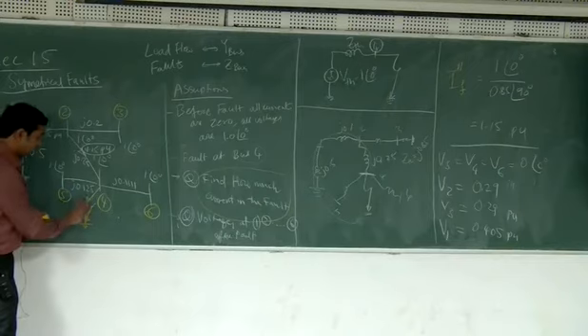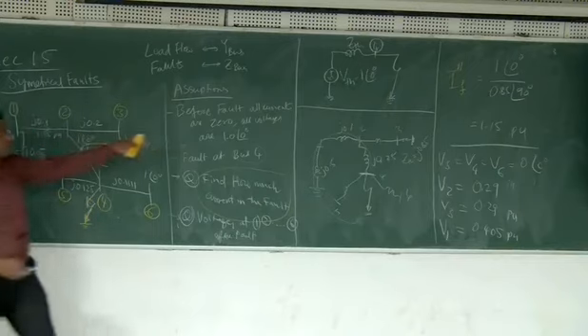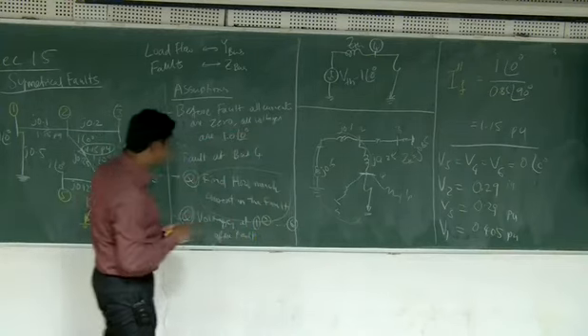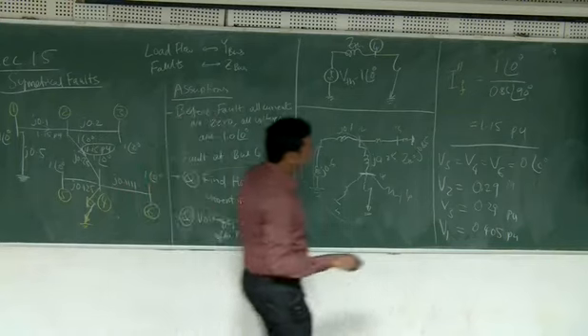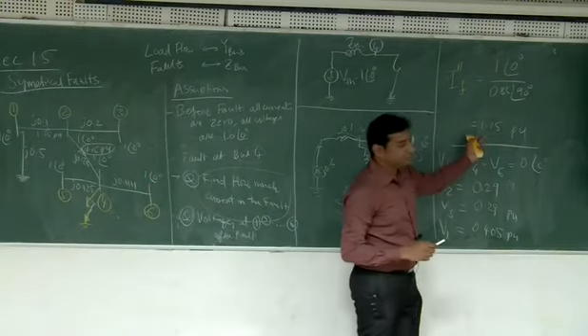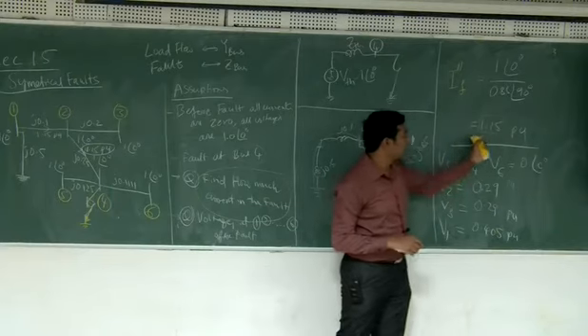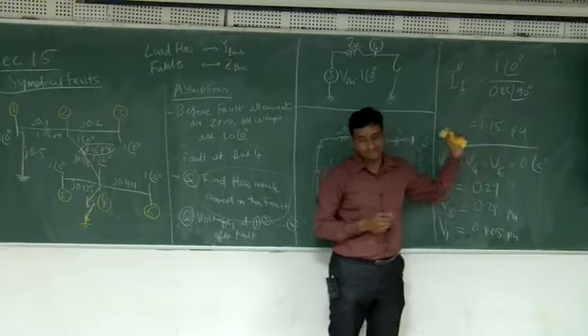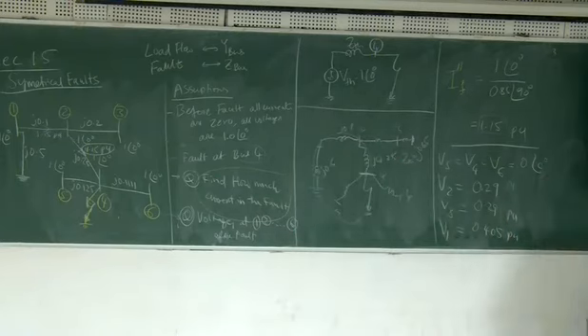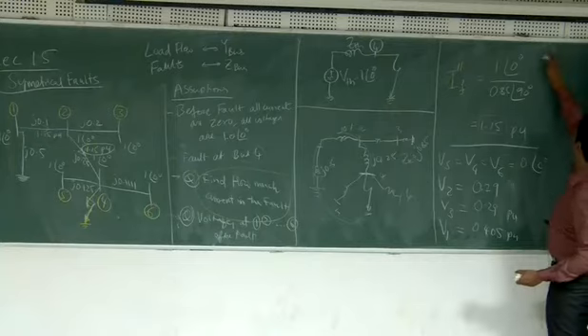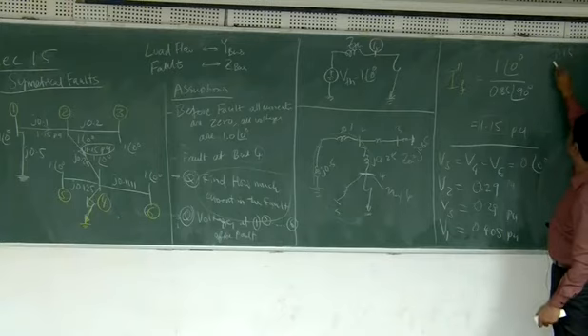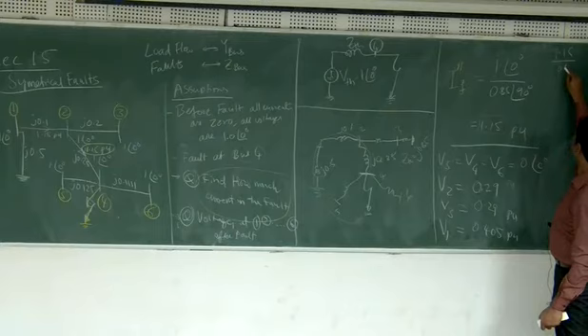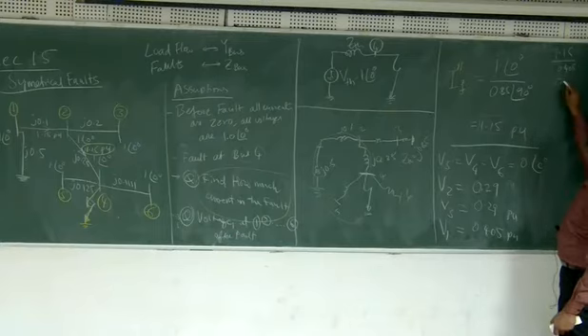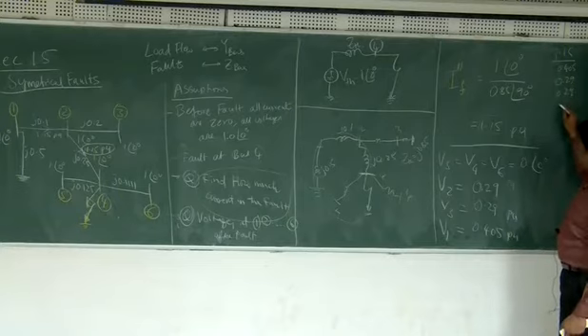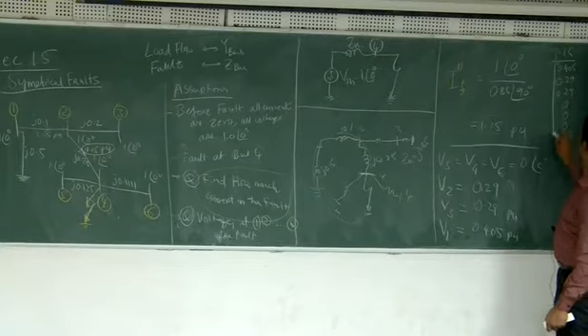If some fault impedance is given, you can consider that in this circuit and then find the rest. Usually this 1.15 is quite less. This is 15% more than the full rating current, but usually it will be even more, because our problem is a little artificial. So remember the answers. Let me write them down here. 1.15 is my fault current, and then the voltages are 0.405, 0.29, 0.29, and then 0, 0, 0. So this is my V.